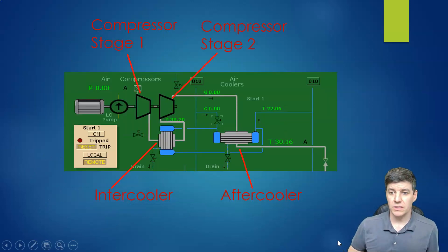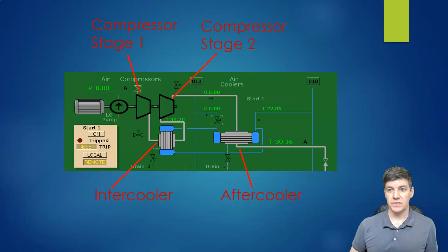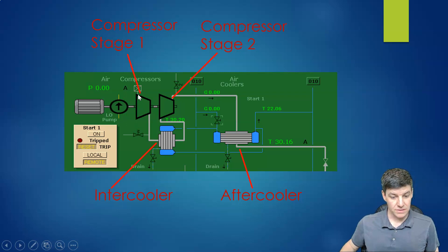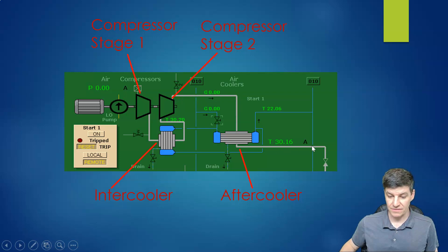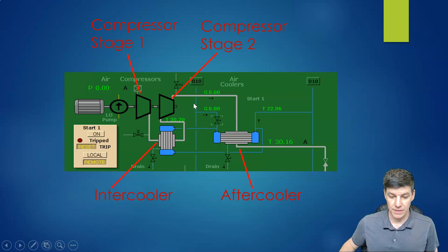Looking at how that's laid out on our simulator screen: we start with our air compressor going through stage one compression, the air leaves and goes through an intercooler, then through a second stage compression, and finally through an aftercooler at the end. Our air compression system is water-cooled, so both the intercooler and the aftercooler are cooled using fresh water.